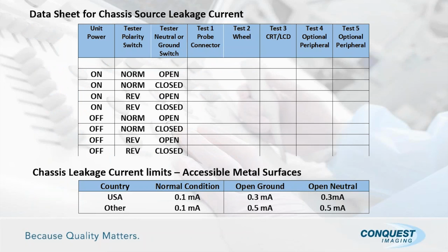This is kind of what I was leading up to at the beginning when I said I have to discuss all the readings and all the procedures independently. But in reality, when you're in the on position with normal polarity and open neutral, you want to do every test while you're in that condition, so you're not continuously shutting the system on and off as you go to the different leakage currents and lead-to-lead currents and such. So you need to stay in the one mode and make all your readings. It will save you a tremendous amount of time.